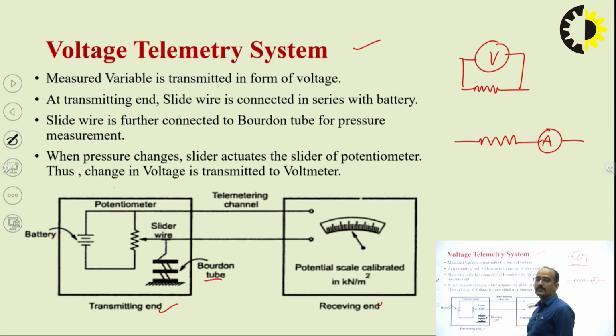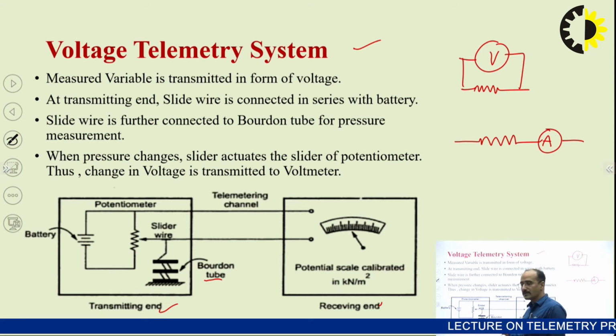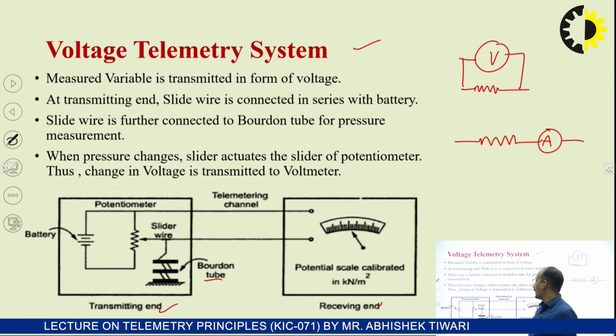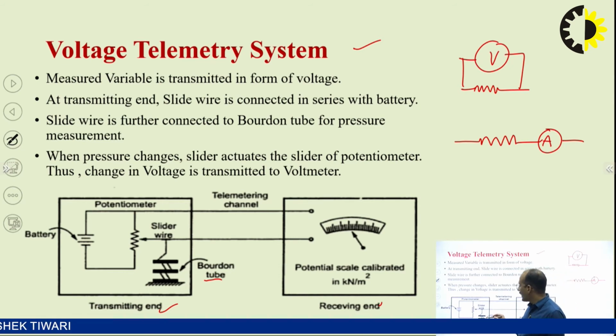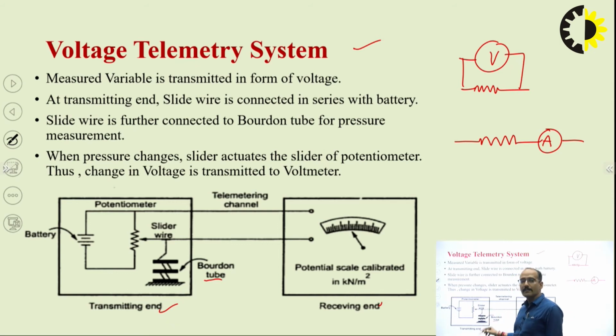In the Bourdon tube, you are applying pressure. When pressure is applied, its dimensions change due to compression and expansion, and the slider wire connected with the Bourdon tube moves, creating displacement. That displacement changes the variable resistance, and due to that change in resistance, the voltage drop across this point also changes. This voltage change is calibrated with reference to the pressure applied to the Bourdon tube.